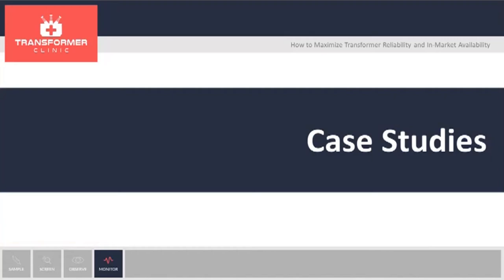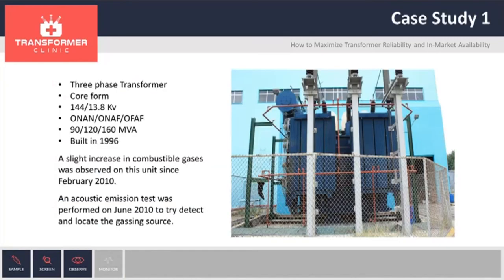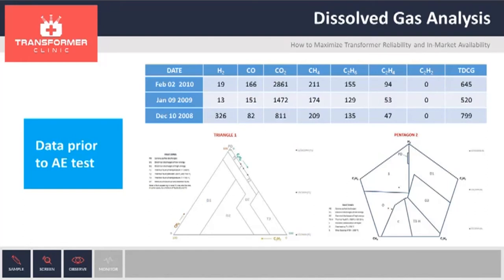The first case study is a transformer we tested in South America. This is a 160 MVA transformer built in 1996 — a core-form transformer. We did a test because the transformer started gassing in February 2010. The main gas on this DGA is ethane. Ethane indicates a low-temperature fault on the transformer. When applying the Duval Triangle, we can see the fault started on low-temperature fault T1 and it moved to a medium-temperature T2. Using Pentagon 2, we can see that the fault at the beginning was stray gassing and later evolved to an overheating.